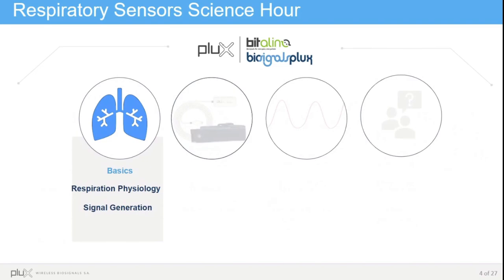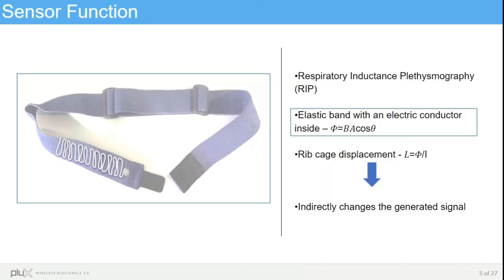Starting by the basics, I will start by explaining how the sensor works. The RIP sensor is composed of an elastic band with an electric conductor inside. The sensing element is embedded in the chest strap fabric, as you can see in the figure in white, and spans its full length. The conductor is rolled around the body, which will be the core of the coil formed by the electric sensing unit.